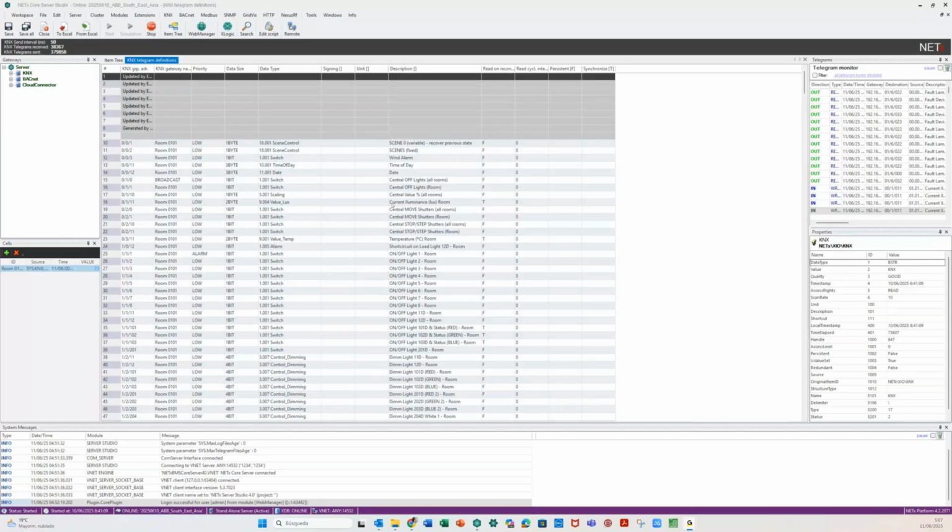This is the way we make the BMS able to connect to these field devices and recover the information from the very beginning, when the BMS starts. So it's very important to use read on reconnect. These were the most important things to do for KNX.